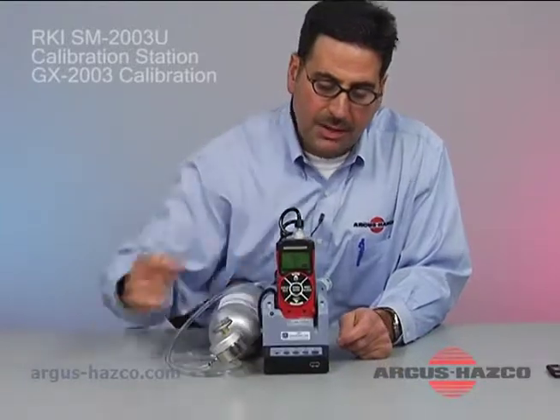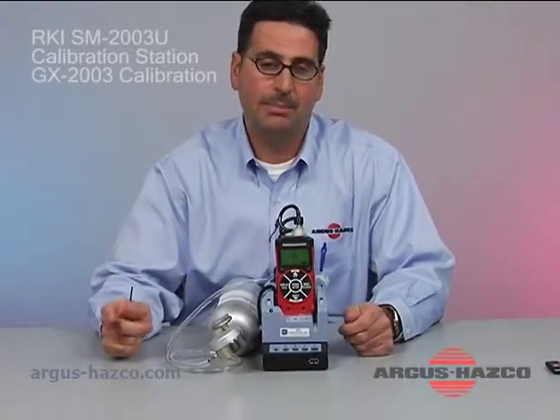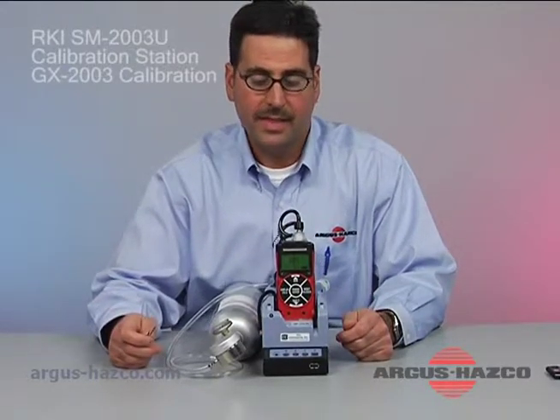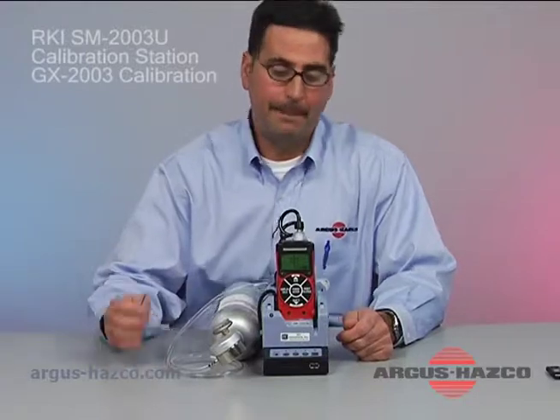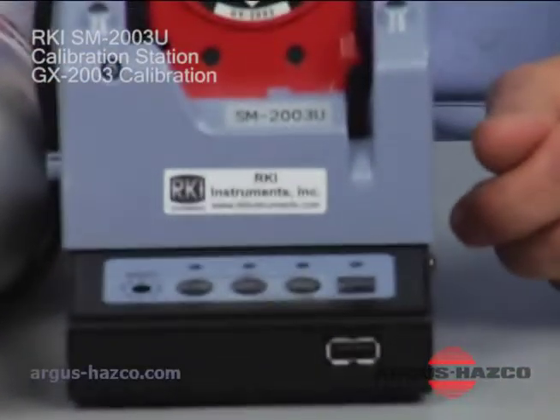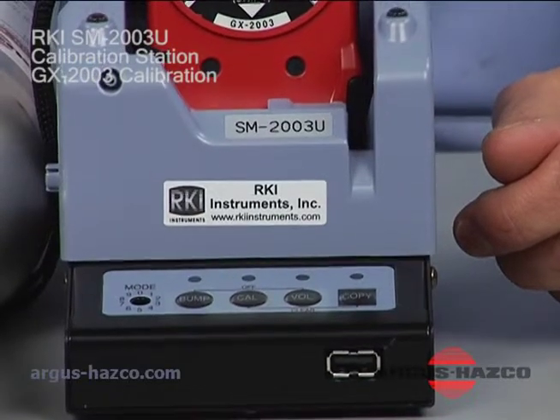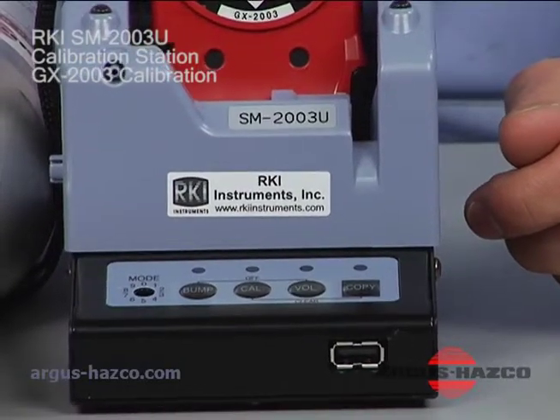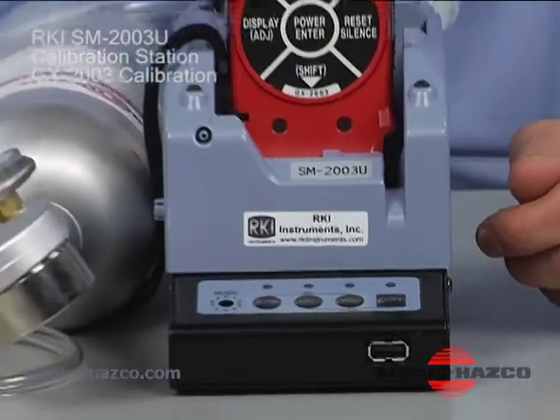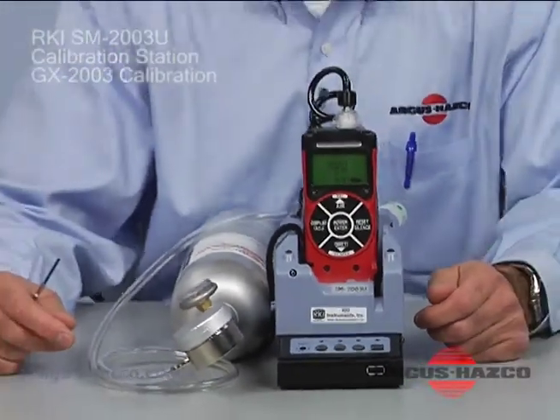You also have several other keys. There is a cal button, but the cal button, if you decide not to bump and go directly to cal, you can just push the cal button. That is an option that allows you to pick the button that you feel best will suit the way the gas is flowed to the unit, and if you're looking to just challenge or bump the instrument, you have that option.